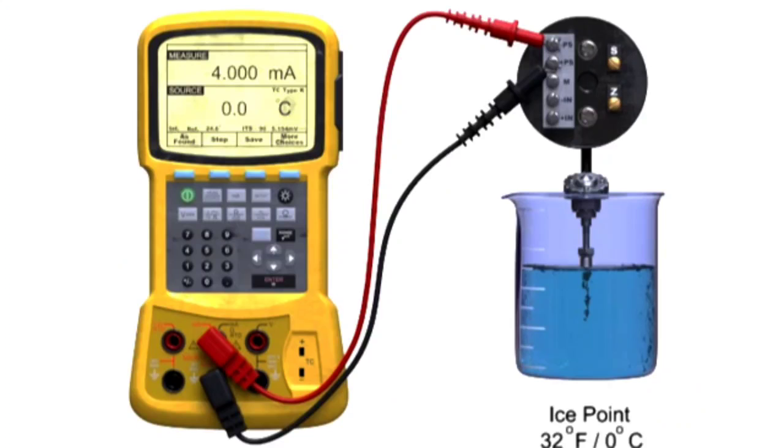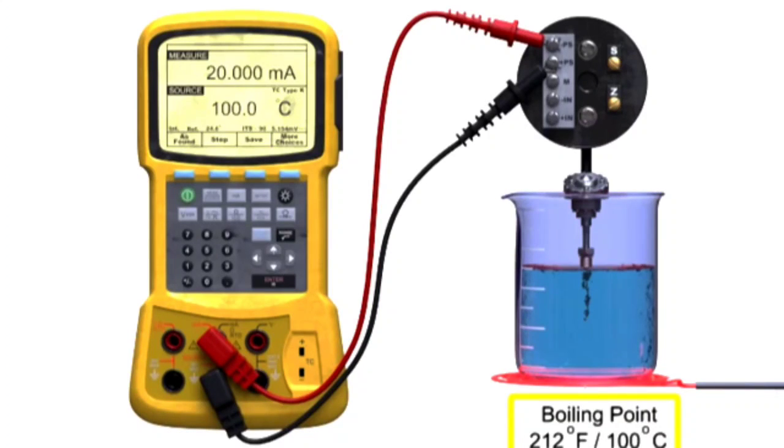To perform the measurement, the process calibrator is programmed to the specific TC type. The accuracy is determined by measuring the temperature of water at 0 degrees Celsius and 100 degrees Celsius, representing freezing and boiling points of water.